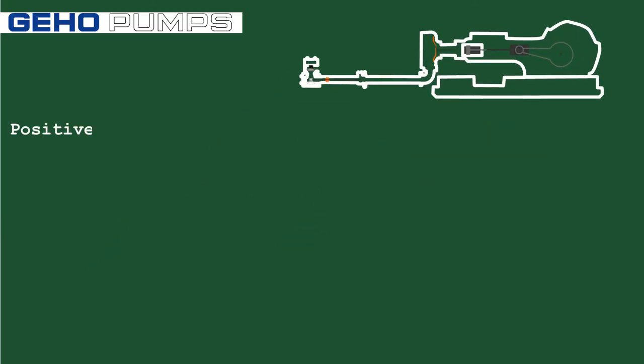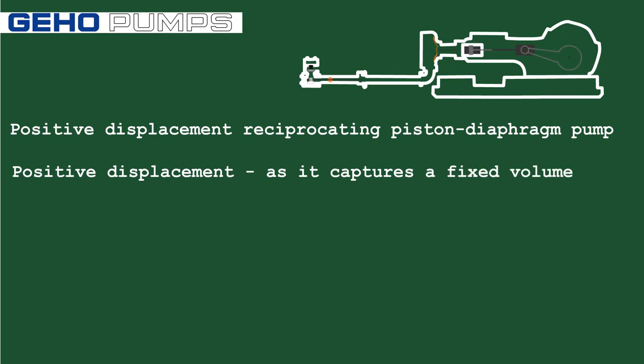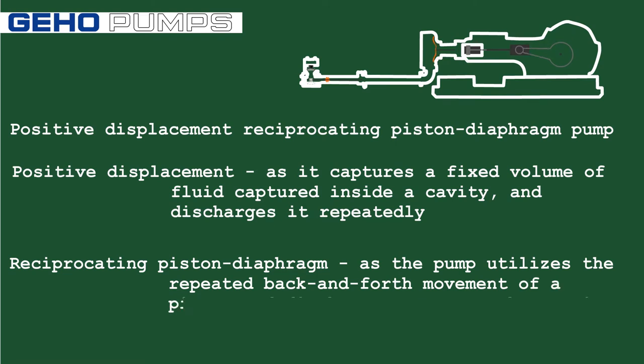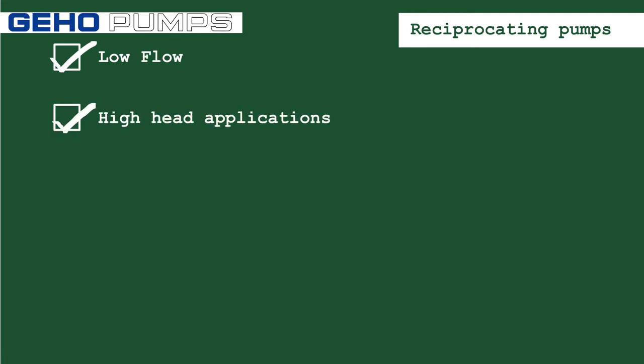The GEHO is a positive displacement reciprocating piston diaphragm pump. It is positive displacement as it captures a fixed volume of fluid inside a cavity and discharges it repeatedly. It is reciprocating piston diaphragm as the pump utilizes the repeated back-and-forth movement of a piston and diaphragm to create that cavity. Reciprocating pumps are generally designed to pump in low-flow, high-head applications.